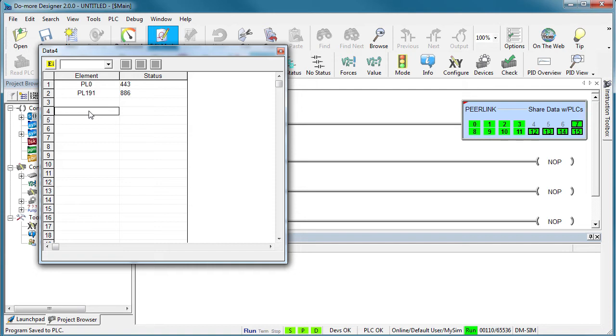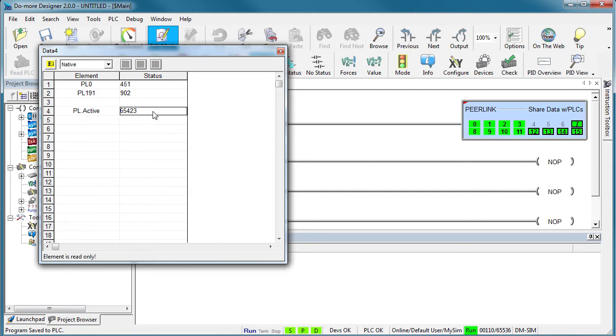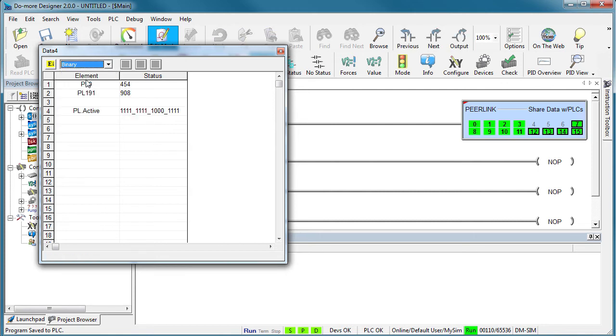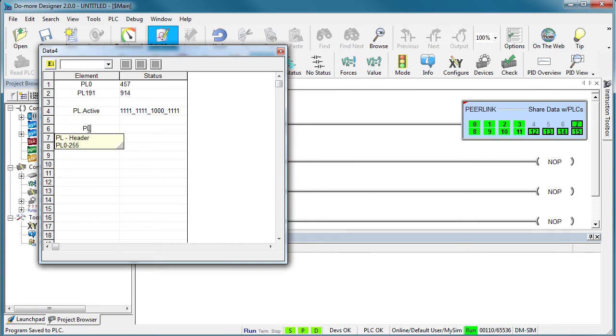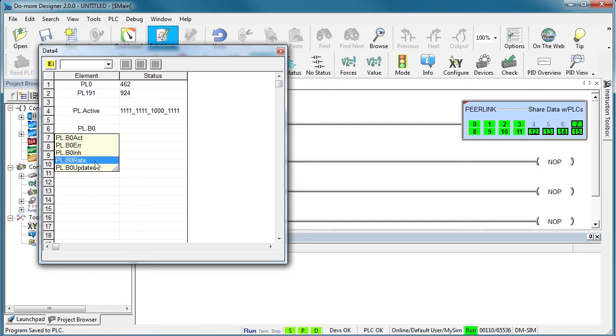PeerLink is updated about 10 times a second as long as the instruction is enabled. And look at this – there are all kinds of status bits you can use. If we take this one and switch it to binary, the ones tell us which blocks are active. Then for each block, let's look at block zero. You can tell if the block is being used, if there are any errors, what the current update rate is and if it has been updated recently. And you can inhibit a block if you temporarily want to take it off the PeerLink network.